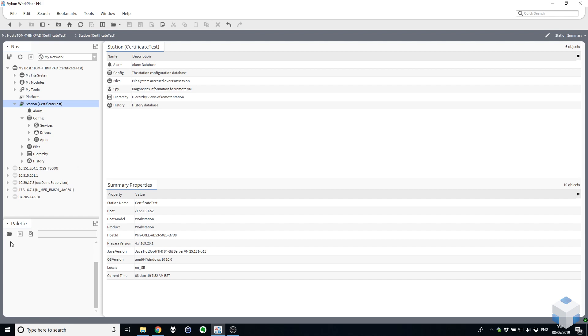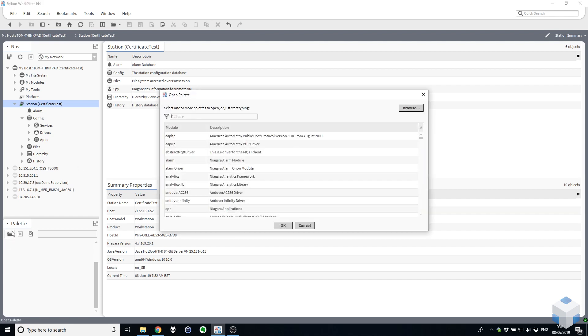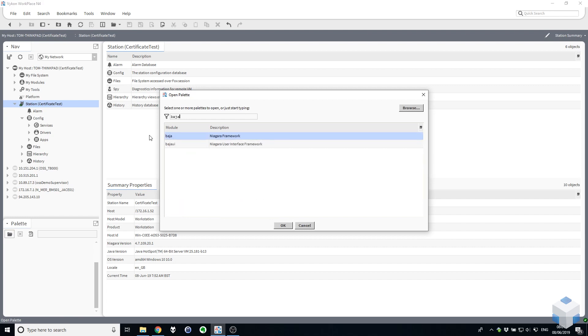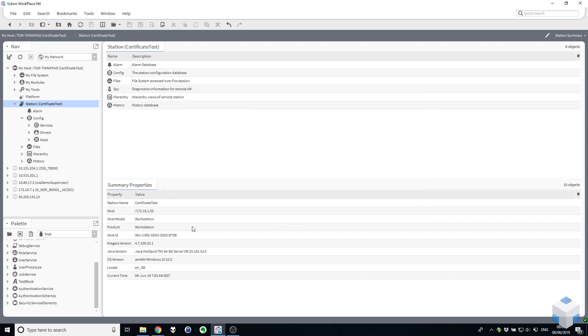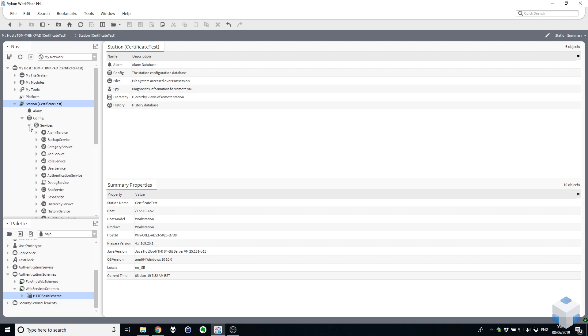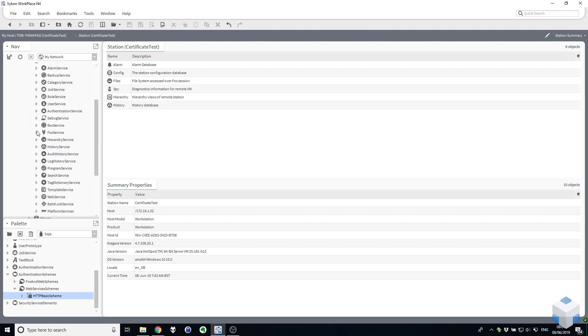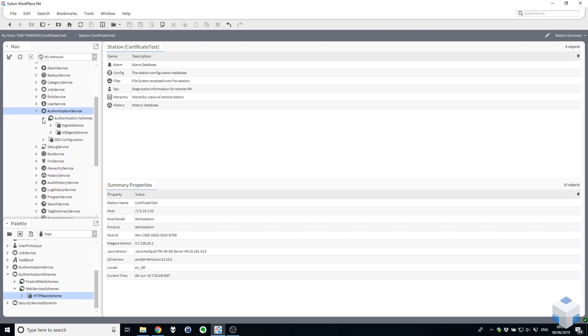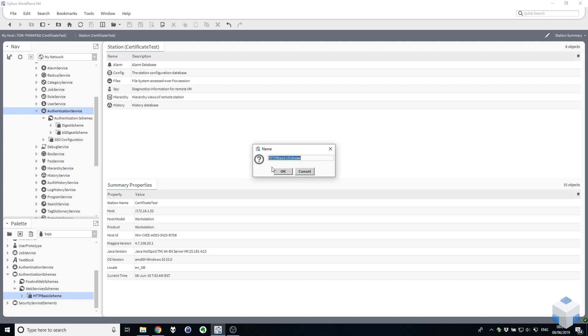So the first thing we need to do is open our palette and look for the Baja module here and expand Authentication Schemes, expand Web Services Schemes and you'll see the HTTP Basic Schemes here. So we need to add that into our Station's Authentication Schemes. So under our Station's Services and Authentication Service, Authentication Schemes, if we just drag the HTTP Basic Scheme, that's in there.